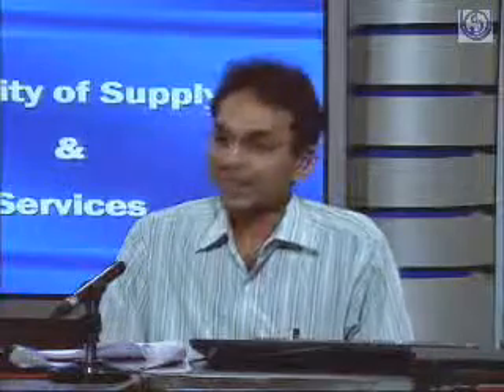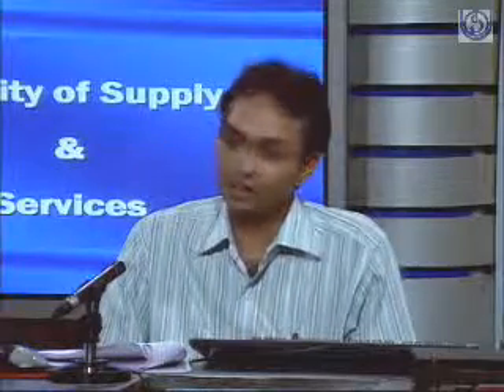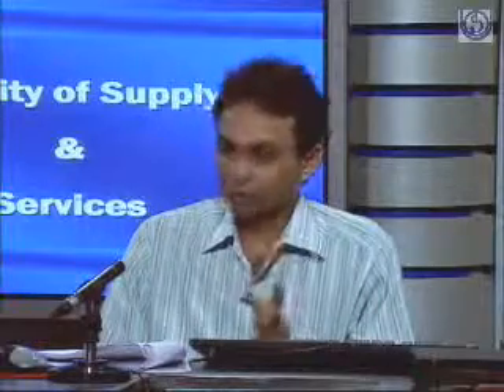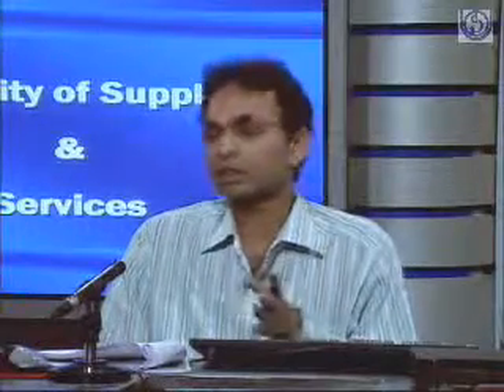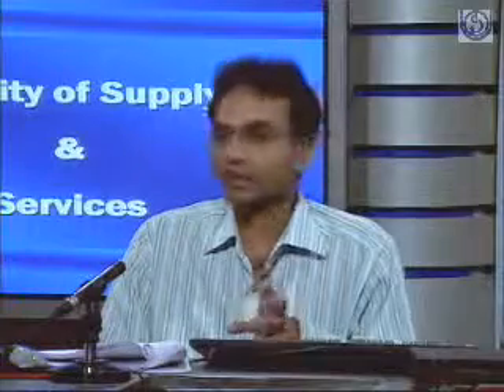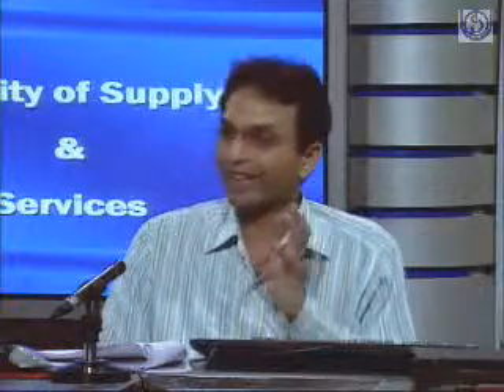However, few regulators have even asked to increase this frequency. For high tension, they have segregated further - if the load is more than 10 megawatts for any particular consumer, then the meter has to be tested once in a 6-month period. So at the national level, the guiding factor is the Indian Electricity Rules, and in many states, almost 90% of states, this is still the compelling factor.